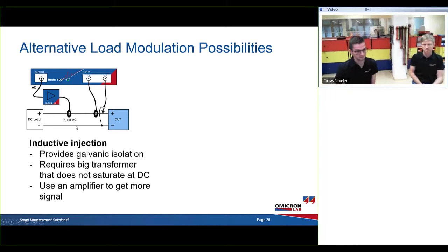Additionally, there are the alternative load modulation possibilities. First of all, the inductive injection. So you use the output of the Bode 100. Additionally, there's an amplifier to inject a higher signal, to get a better signal to noise ratio. Then you can use any inductive injector. You can build one for yourself, for example, or buy one. It provides a galvanic isolation, but if you have high DC voltages, you also need a big transformer which does not saturate at the DC currents that you have. Did I say voltages? DC currents. As I mentioned, the amplifier at the output gets a higher signal.